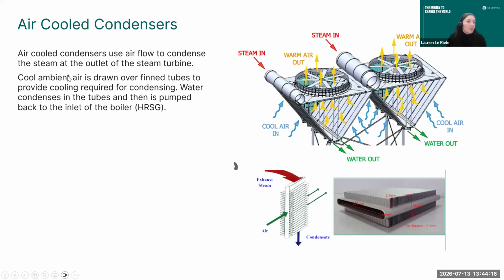Starting with the air-cooled condensers: they are indirect heat exchangers that use airflow, ambient air, to cool down the steam and condense it. You can see visualizations here - steam comes into these big header pipes, passes through these fins, and then condenses. The volume comes in very large and comes out very small as it condenses. Air is drawn through fans, sucked over these fin tubes to cool down the steam until it condenses into water before it is returned to go back to the power circuit.